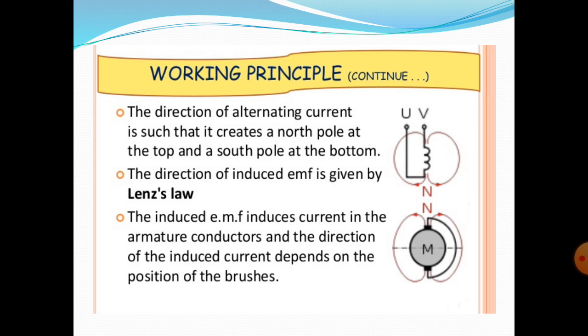In this motor, the armature winding is short circuited through brushes, and generally the brushes are movable. Brushes are made of carbon and placed in brush holders. The brushes are movable on either side of the axis of the stator winding, by which the speed can be controlled in either direction.